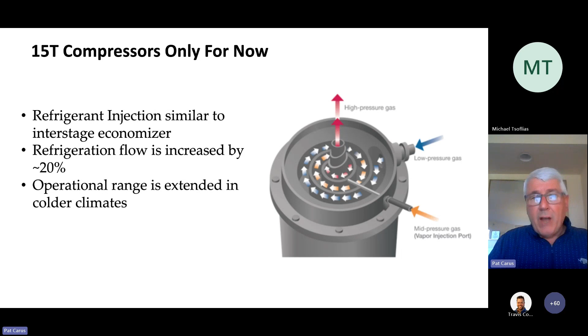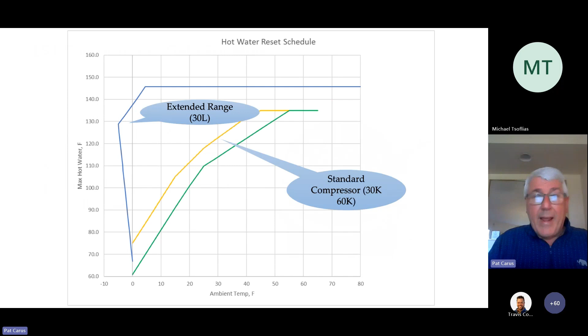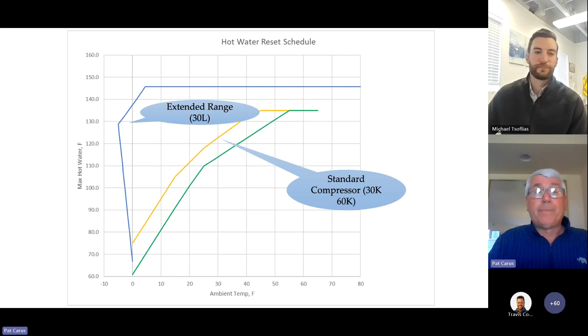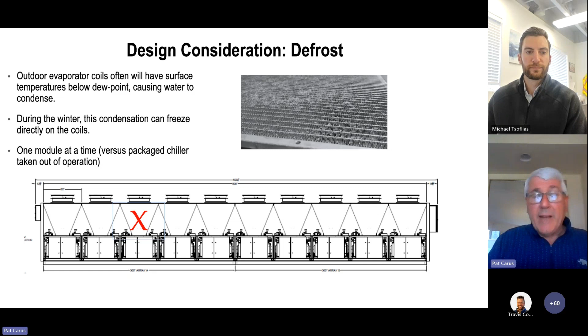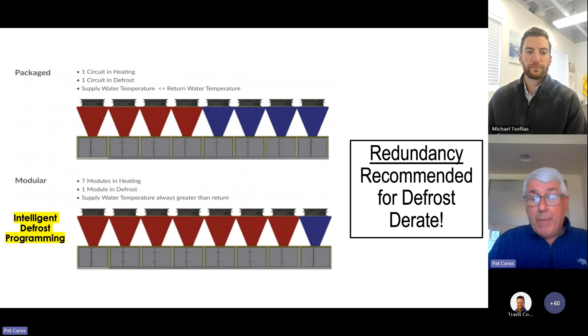So this is essentially how it works. There's just refrigerant injected into the scroll set. It flashes off, and it allows the operating envelope of that scroll to grow. Extended range, you see that on the right side, where we can get down to 0 or even a little bit below 0. Defrost, we have that all covered. One machine at a time in a particular array versus the competition, which doesn't do it that way. We have a unique way to handle defrost.